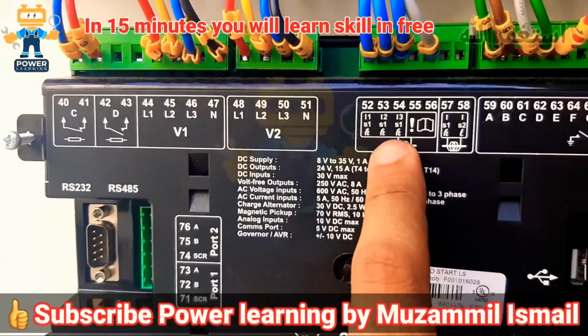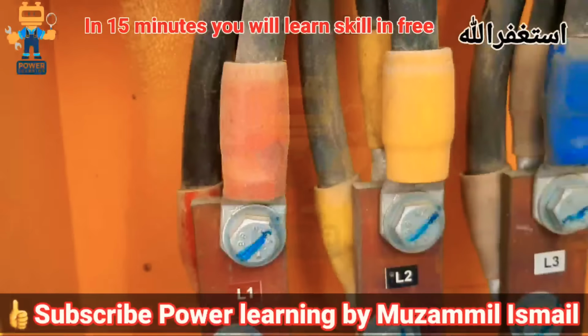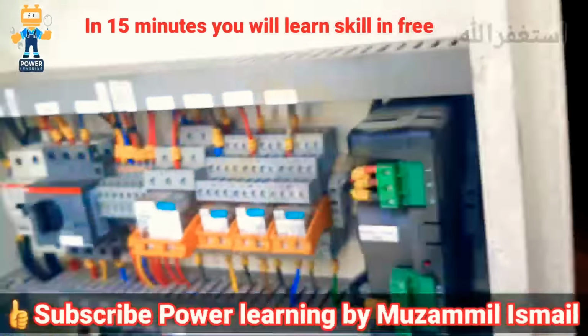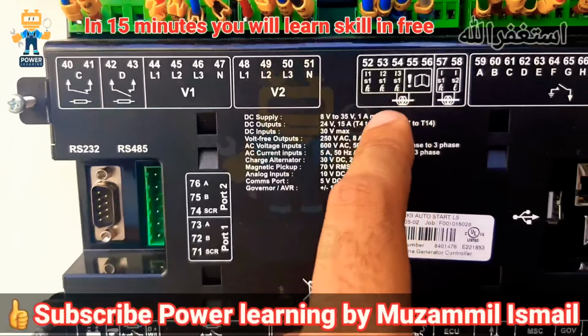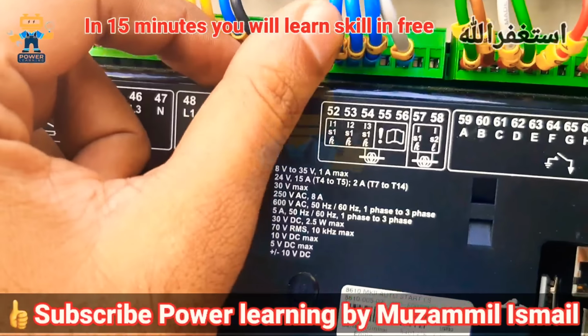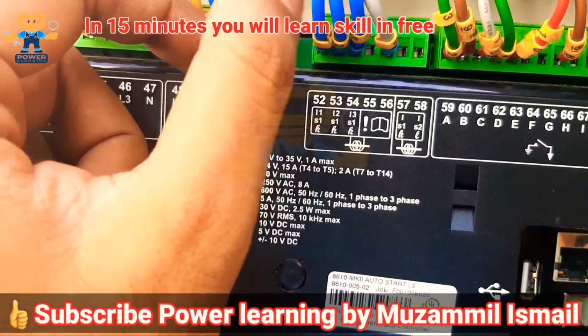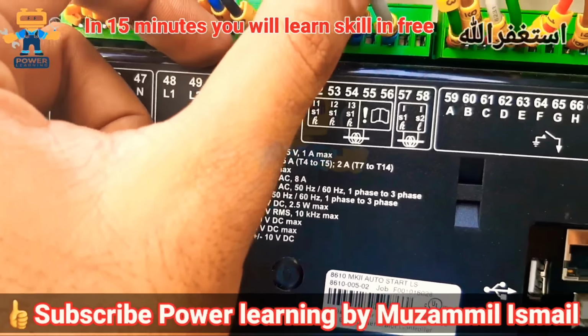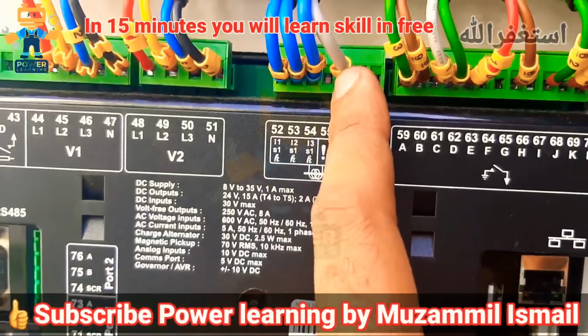Okay, which is monitoring the current transformer now inside the alternator, so I am unable to show you, but all these cables are coming from our 3 CTs. Number 1 from the red phase, number 2 from the yellow phase and number 3 from the blue phase, and this is the common of our 3 CTs.